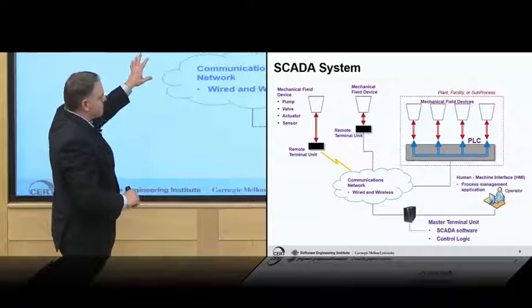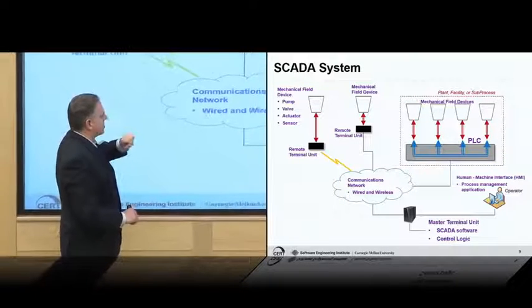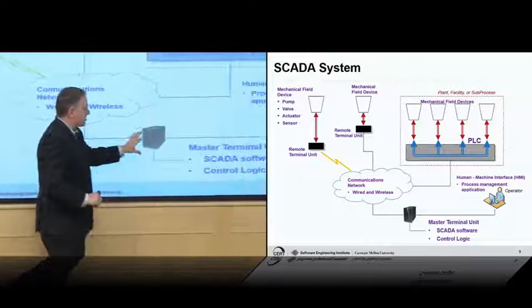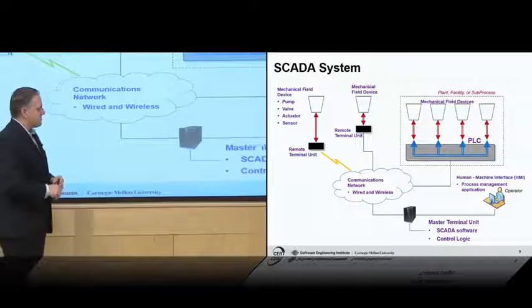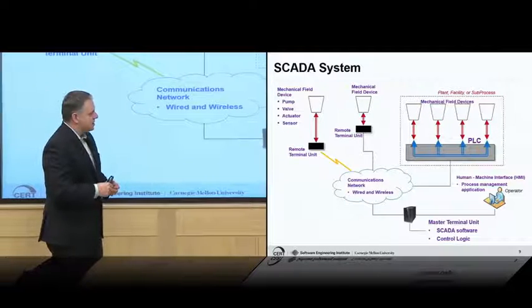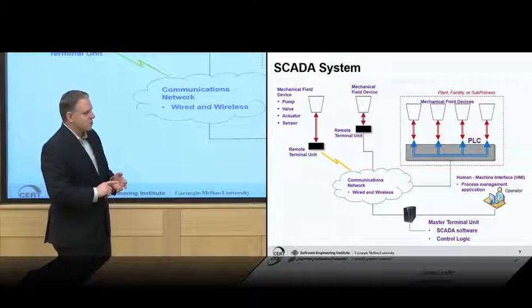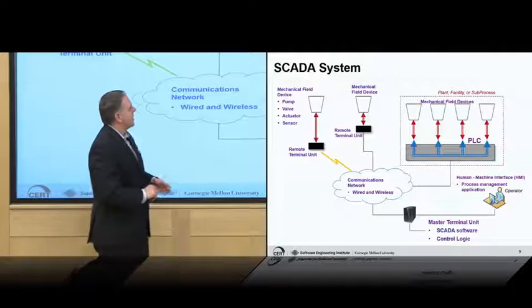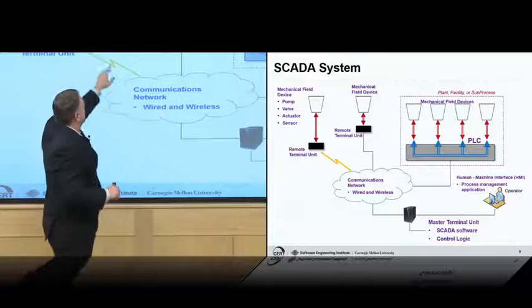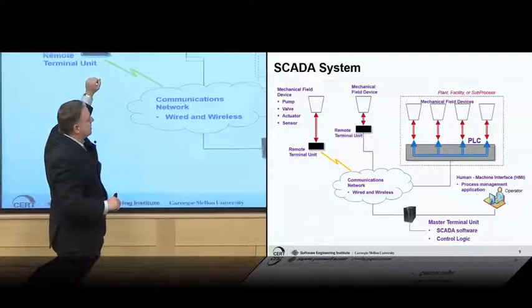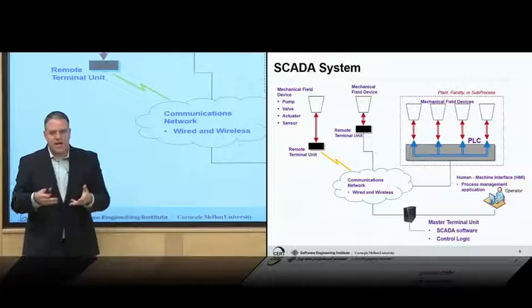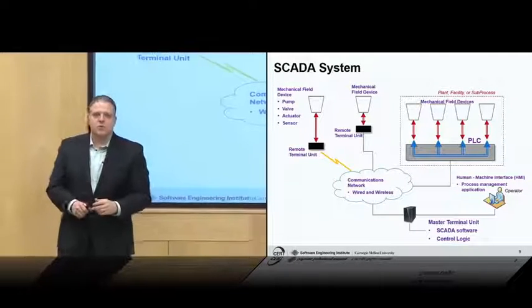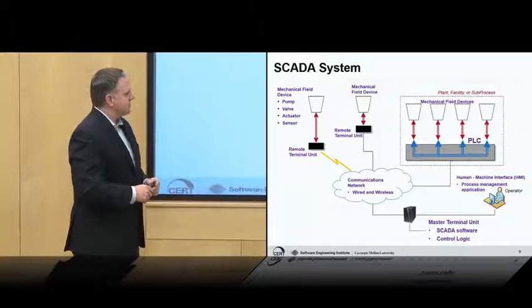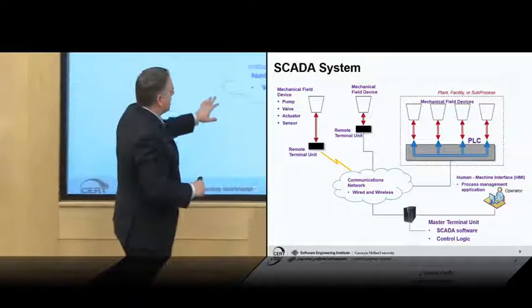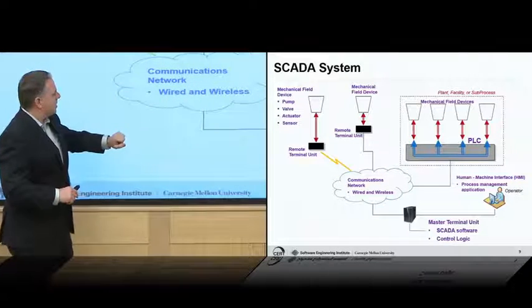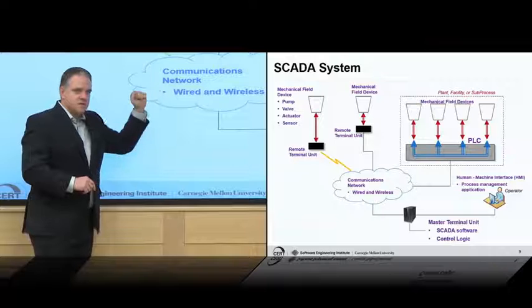So you probably have multiple mechanical field devices and multiple remote terminal units. All of those are communicating with a master terminal unit down here that has some type of control logic in it, presenting things to an operator either through SCADA software or some type of HMI. And then you've got all of these PLCs up here - I should have mentioned that here in the black box. You've got all these mechanical field devices communicating through a PLC to the remote terminal unit, down to the master terminal unit. This is really where challenges start to occur, because traditionally the PLCs or RTUs...